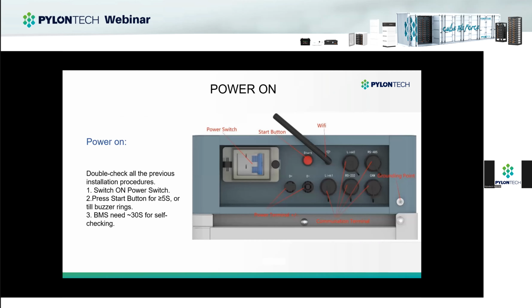If you want to power it on, this is the process. Just press the on button, and the BMS needs 30 seconds for self-checking, to check the communication between the BMS controller and the inverter. If everything is okay, if the BMS controller set communication with the inverter successfully, then the self-checking is finished, and the battery can have output power.